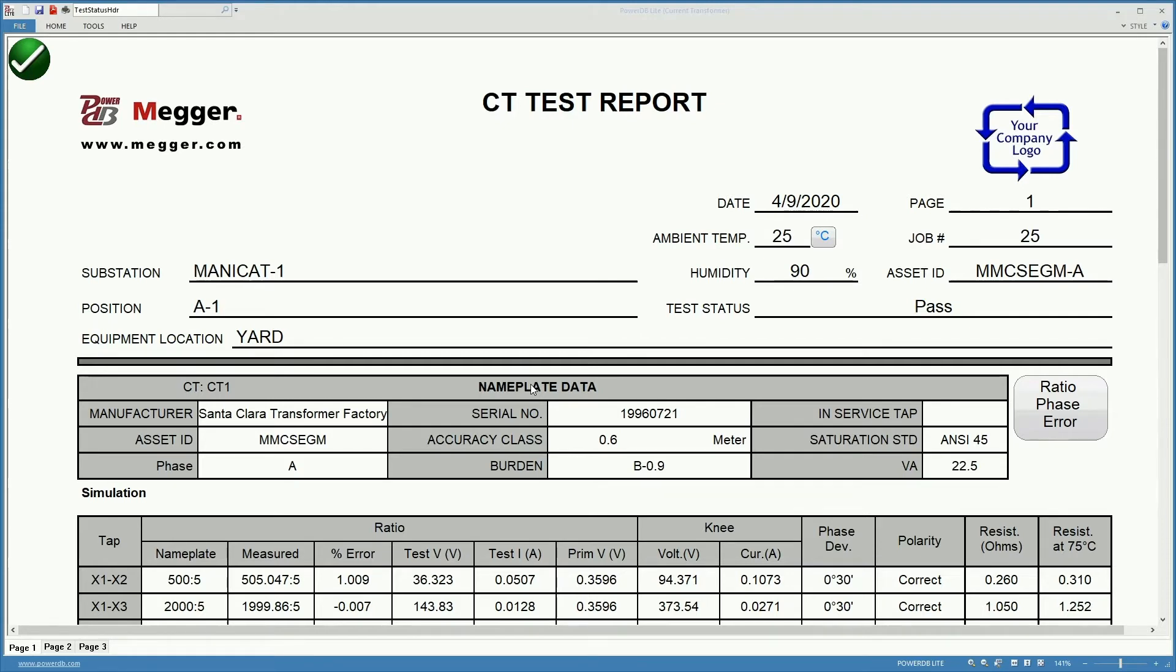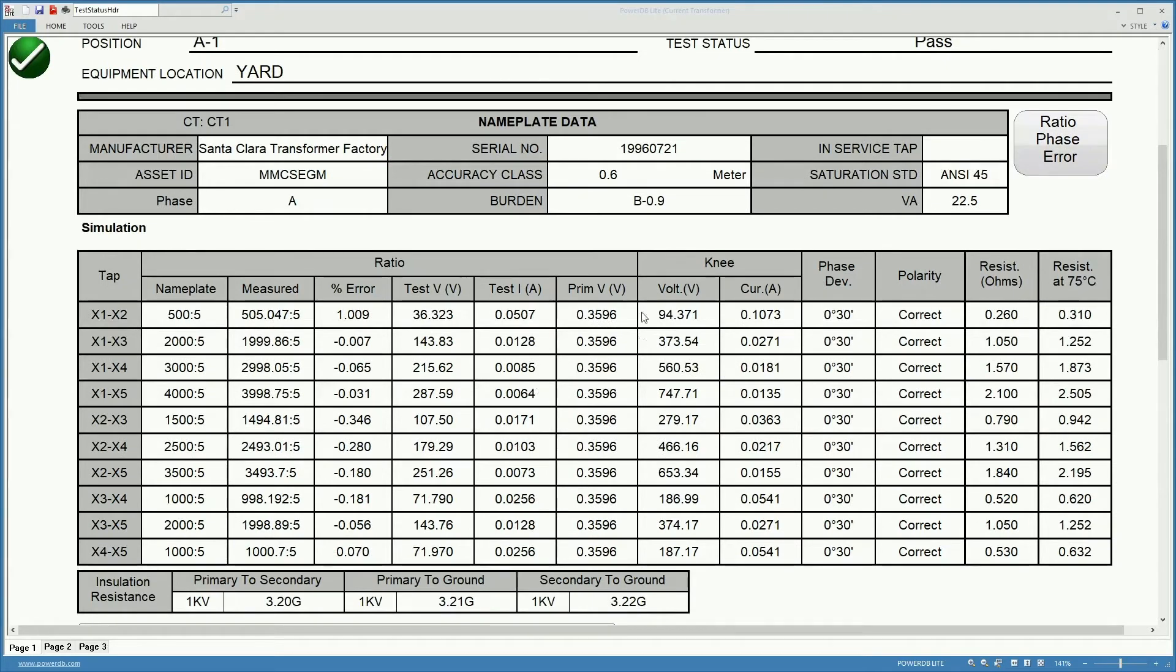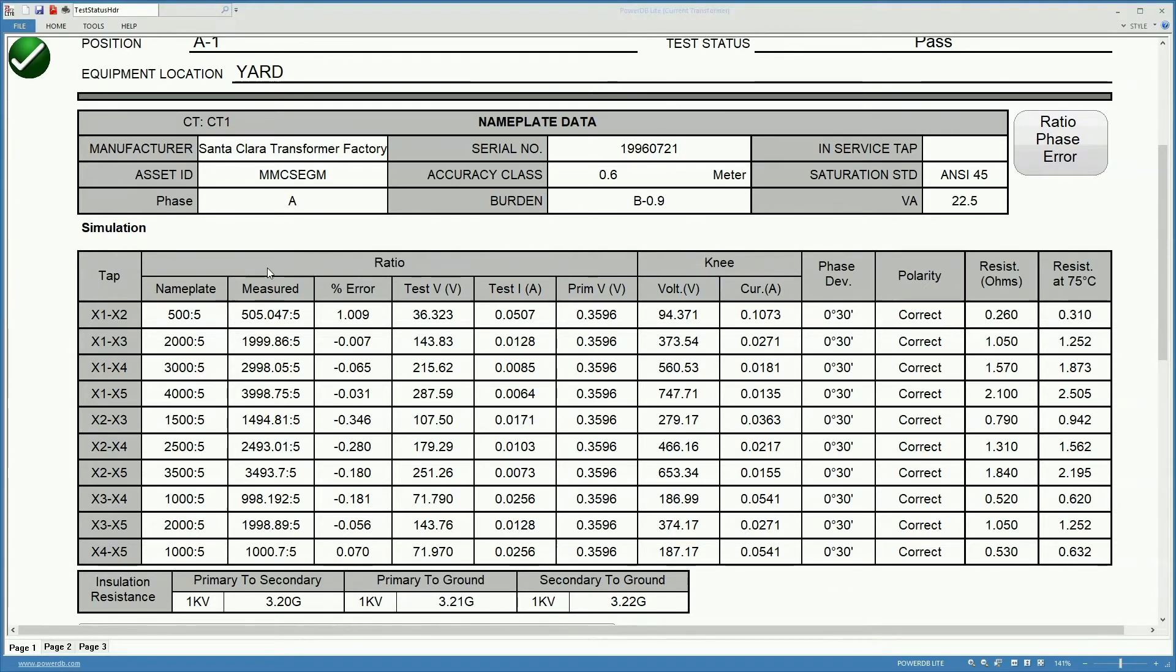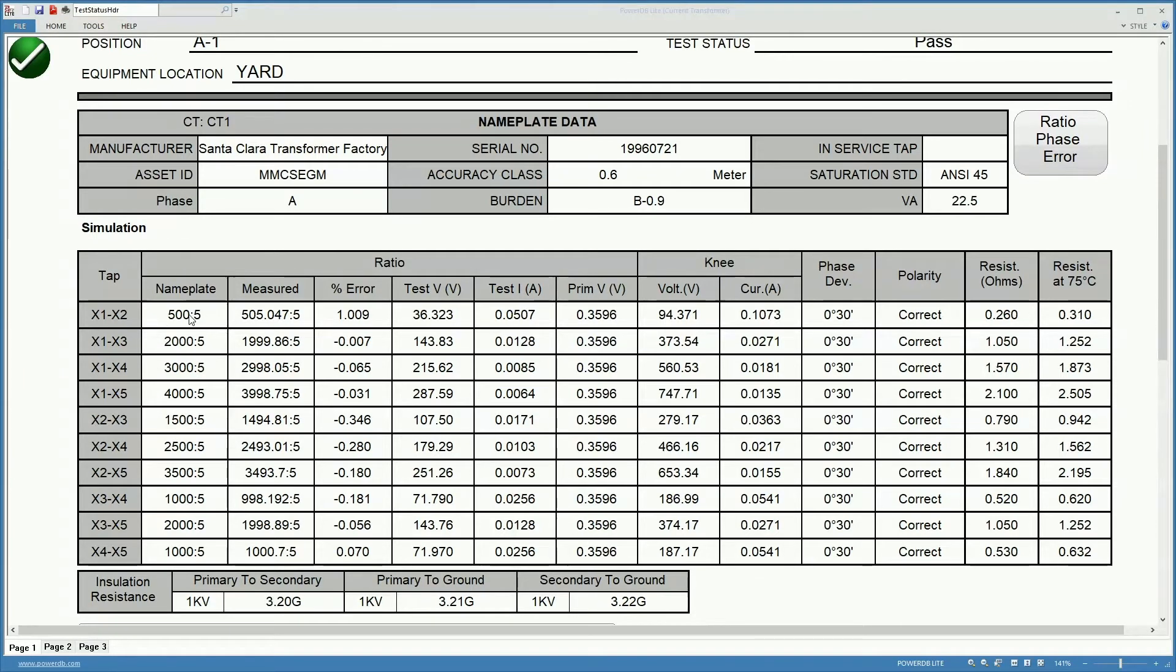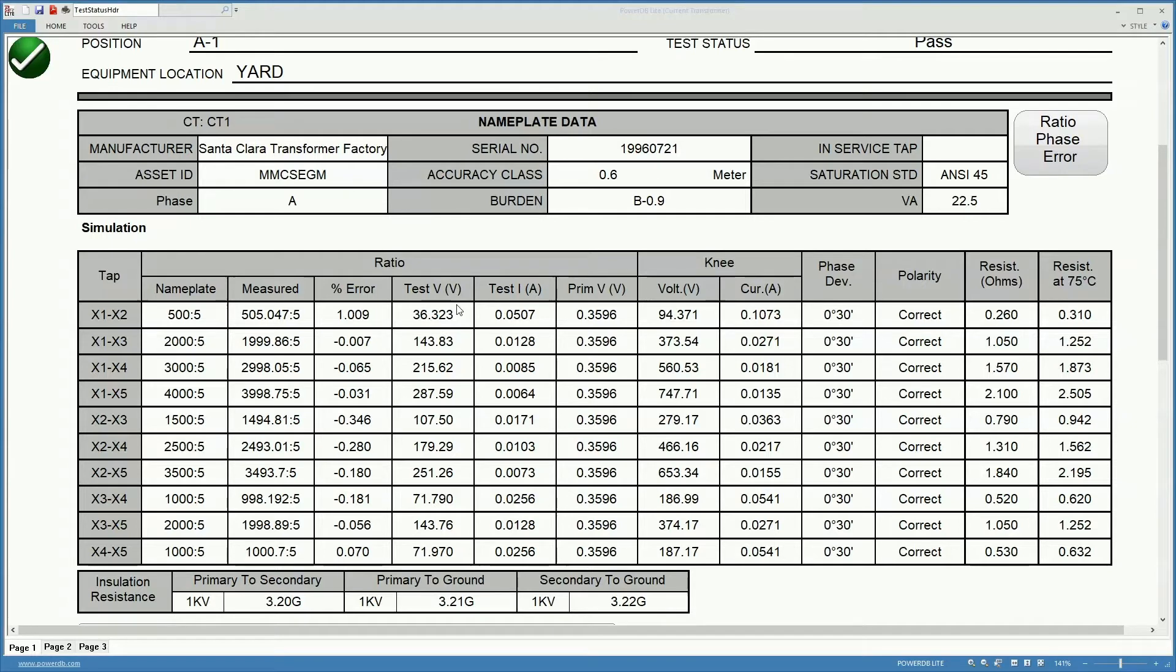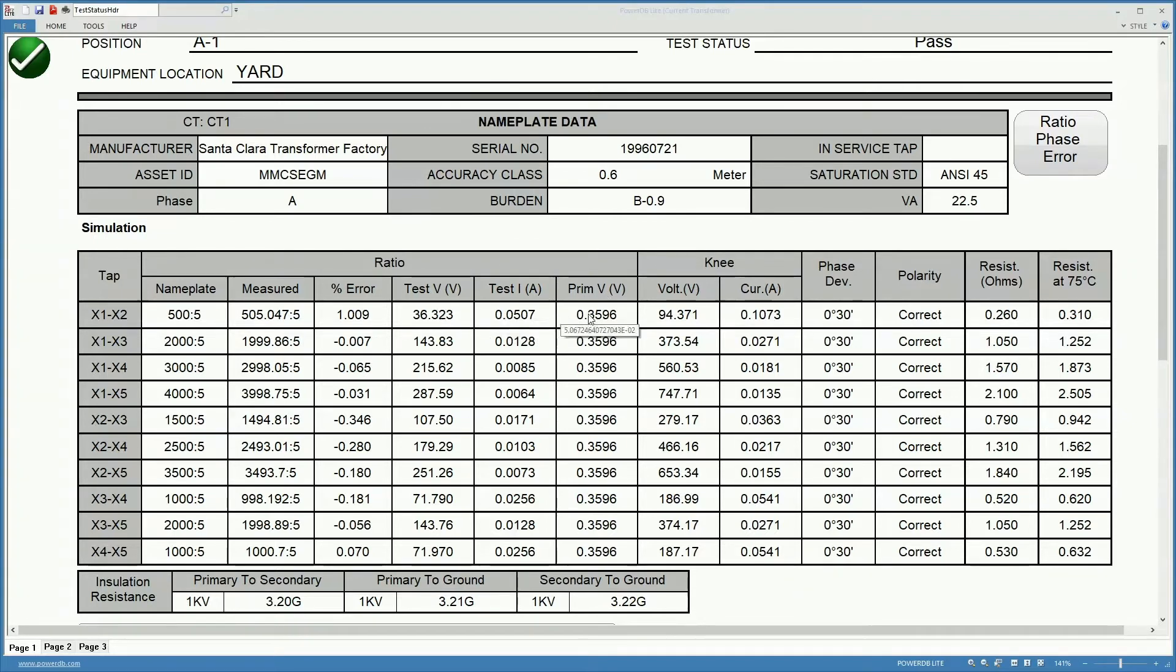The next area consists of the information regarding the ratio values obtained during the test and the errors obtained if we configured the nameplate information for the ratio on the different tabs. Then we will get a calculation of the error represented by the difference between the measured values and the actual nameplate values. We get the voltage at which those ratio tests were done and the current that was circulating in the secondary for that tab at that moment. We get also the primary voltage at which the ratio was calculated.